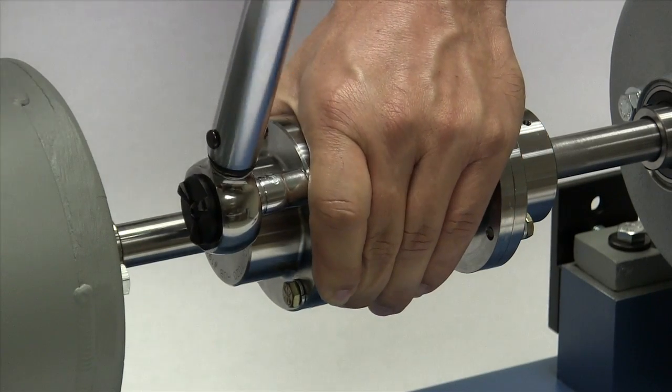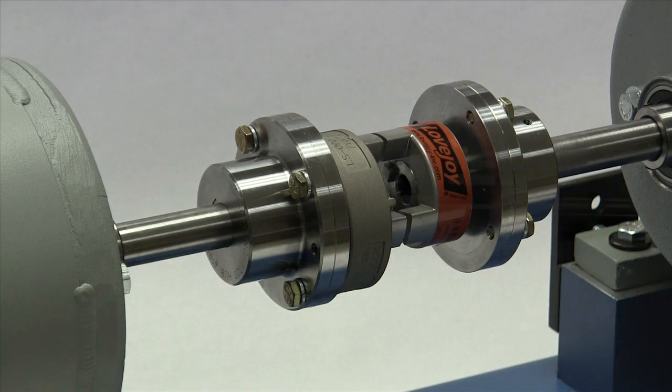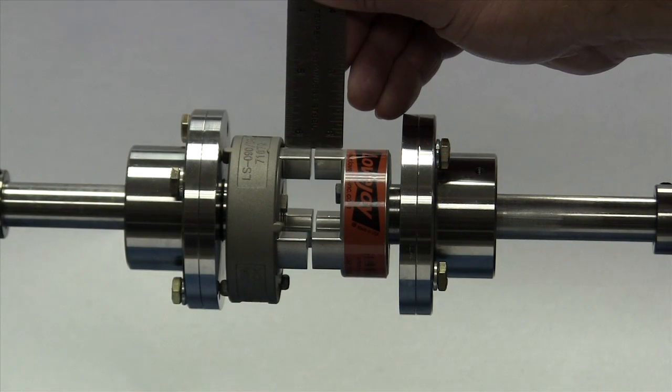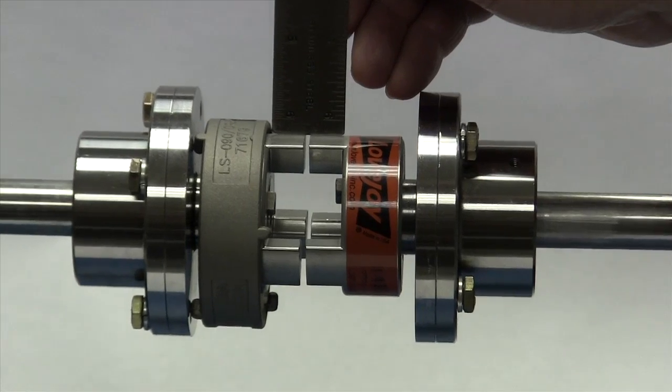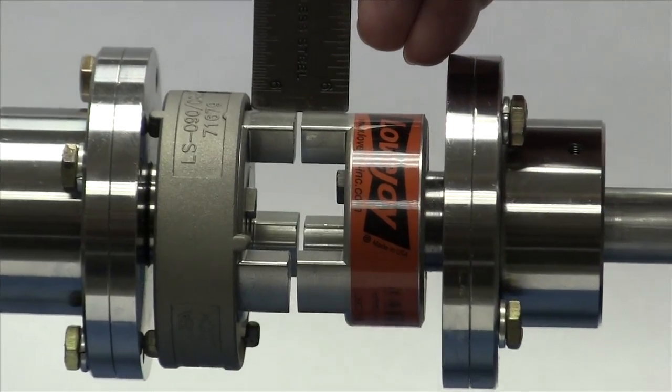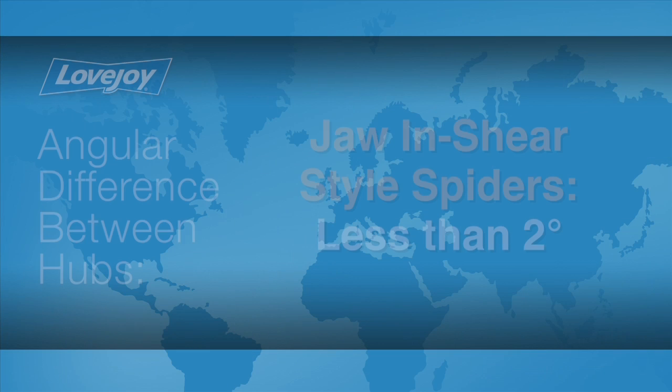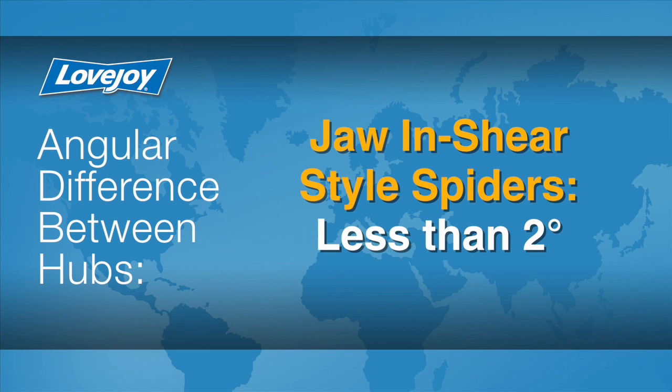We will check the coupling alignment prior to installing the spider. Lay a straight edge across the hubs to check the basic alignment. The offset between the two hubs should be less than 1/32nd of an inch to prevent damage to the coupling. The angular difference between the two hubs should be less than 2 degrees for the jaw in-shear spider. If the alignment exceeds the allowable amount, you will need to realign the equipment to correct this condition.